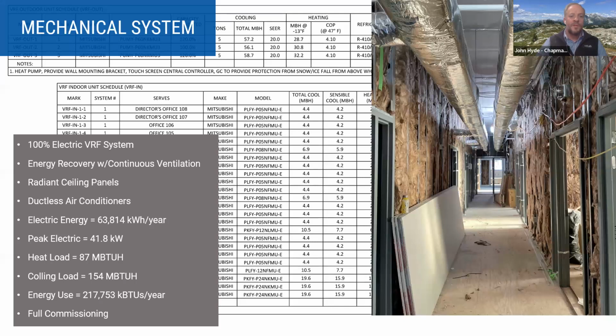So the mechanical system, pretty standard. Since our heating loads are so small, we could go with a fully electric VRF system. We installed the branch circuit controller so we can do simultaneous heating and cooling, or move heat around in the building. If one side needs heating and the other needs cooling, we can move the heat instead of creating it, increasing our coefficient of performance.